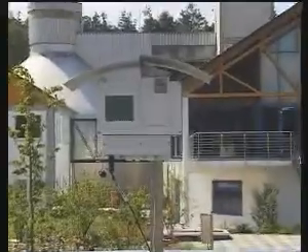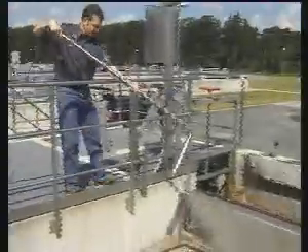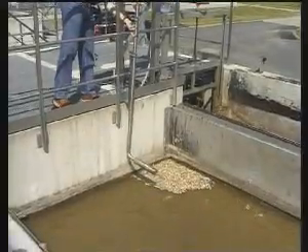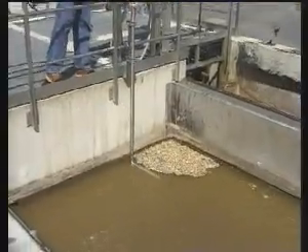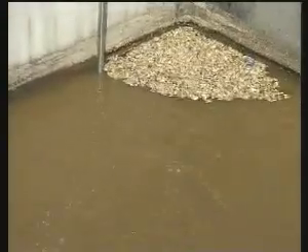With the UV probe, it is possible to monitor the load of impurities in a sewage plant continuously. Highly polluted effluent, for example from indirect industrial drains, can be detected, provisionally stored in buffered tanks, and then released into the cleaning process at the most favorable time.